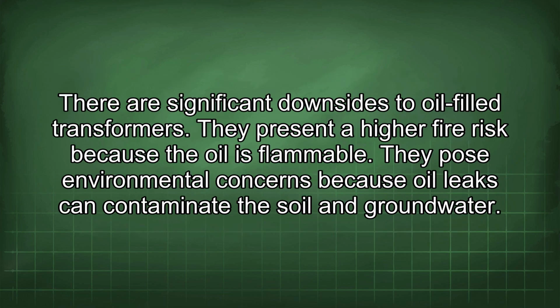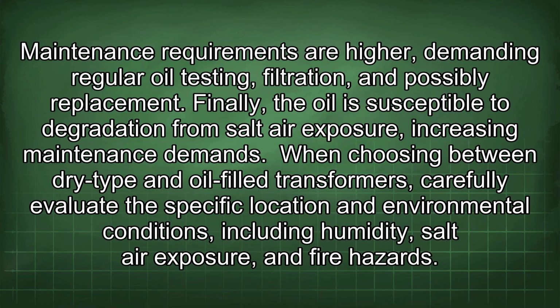There are significant downsides to oil-filled transformers. They present a higher fire risk because the oil is flammable. They pose environmental concerns because oil leaks can contaminate the soil and groundwater. Maintenance requirements are higher, demanding regular oil testing, filtration, and possibly replacement. Finally, the oil is susceptible to degradation from salt air exposure, increasing maintenance demands.